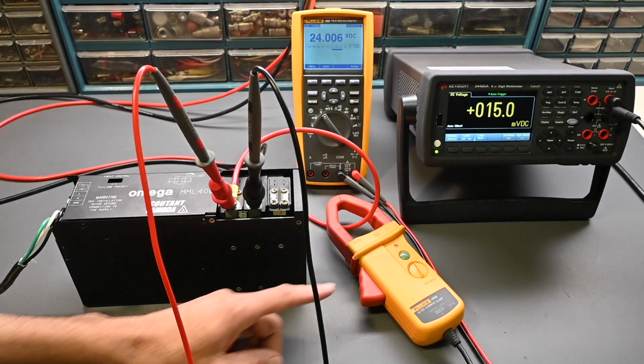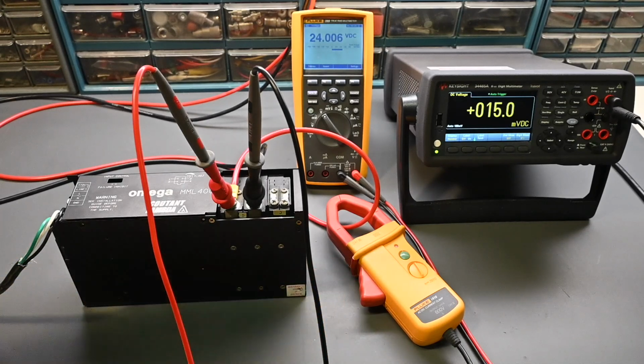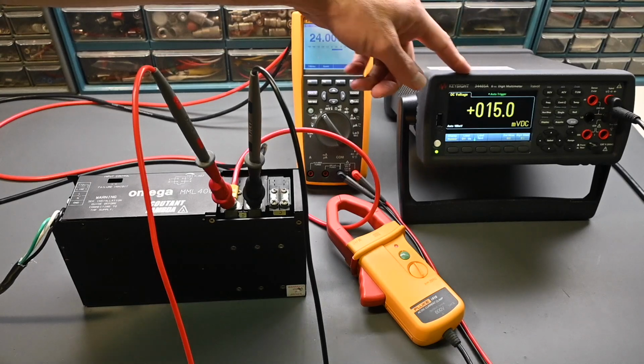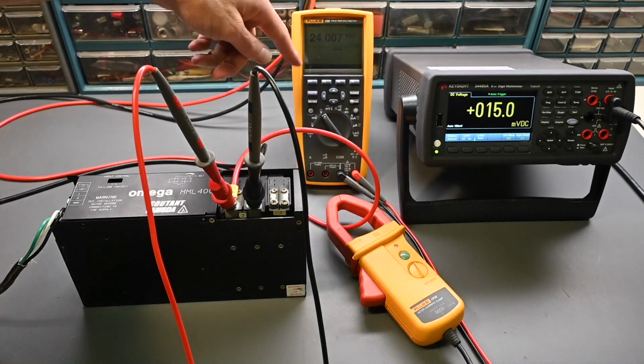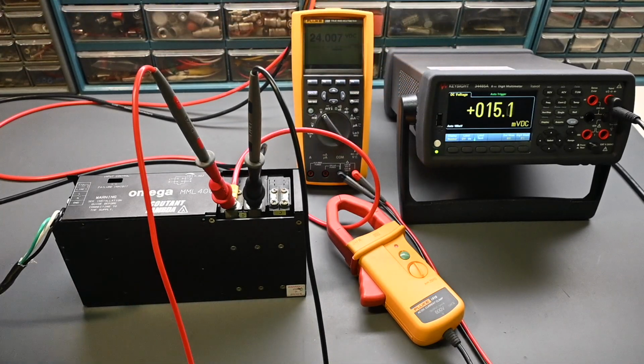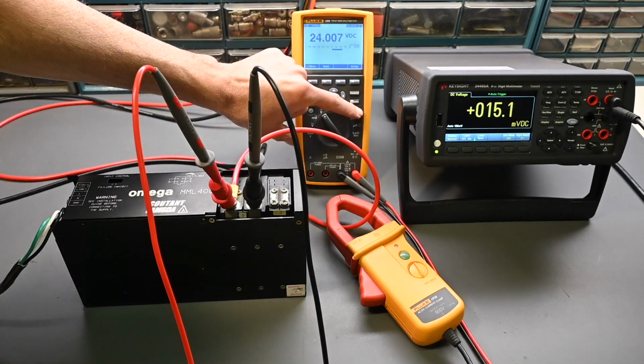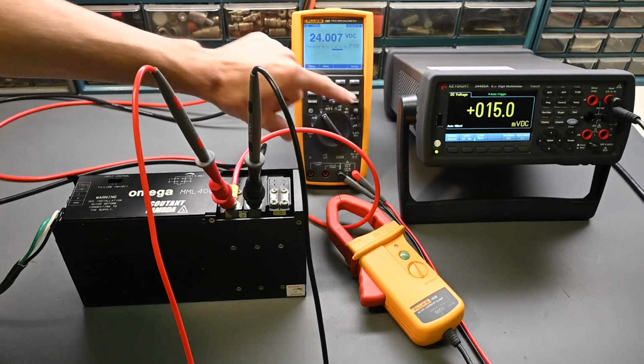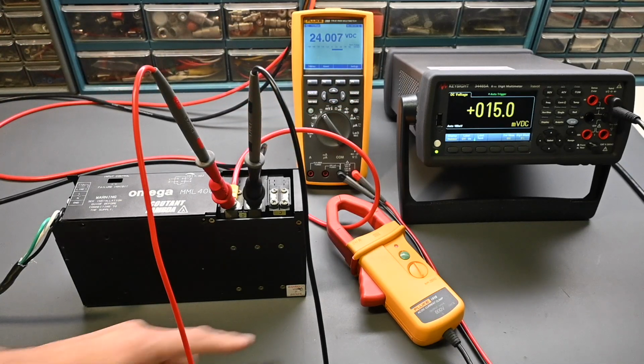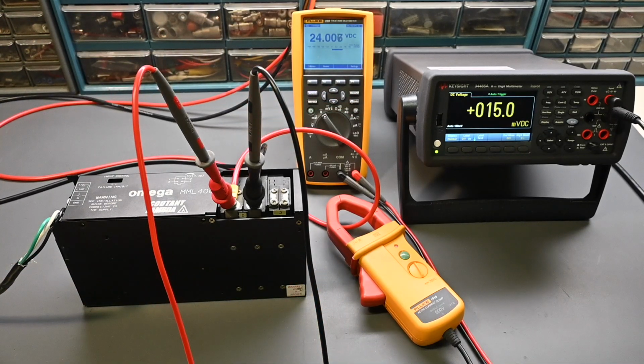Now you may be wondering why I use this current clamp over here instead of just running the current through the digital multimeter. The digital multimeter, whether it's the Fluke or the Keysight, tops out at 10 amps that you could put through those meters. So I didn't want to, of course, blow the fuse because we're going to 15 amps. So I needed to use a current clamp. You could also use an external current shunt, but I don't have one of those. I typically use current clamps.